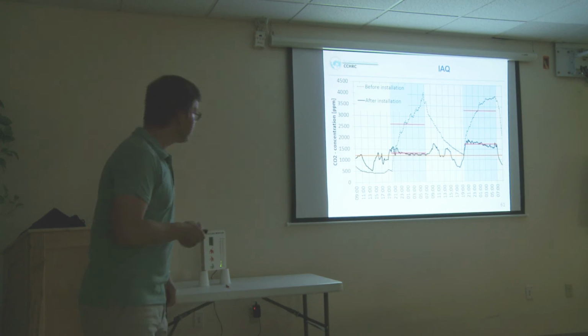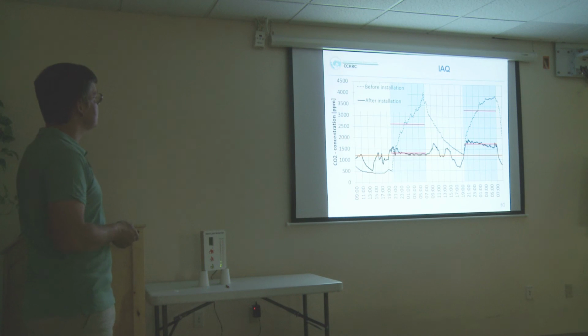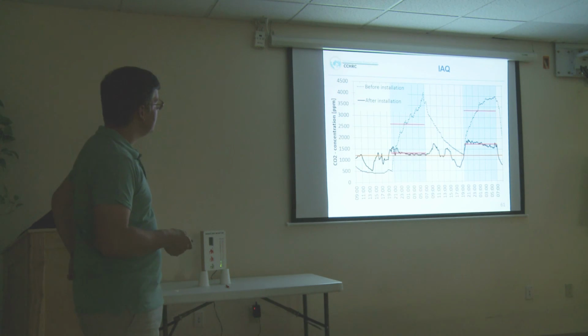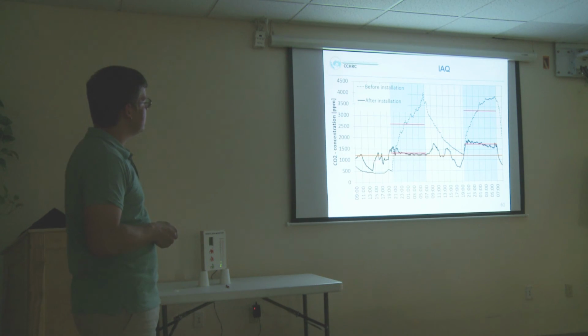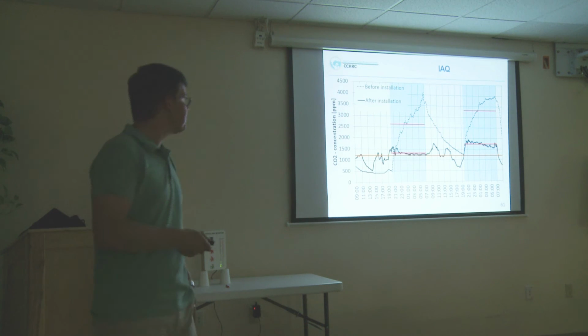So what happened with the indoor environment? We have two nights here as well. This is the chart shown on one of the first slides, and then after we installed the ventilation unit, the nights look like this. We are still a little above 1000 or 1100 ppm, but very close to that, and the second night is also below 2000 at least. You see the ventilation kick in, and now we are at 700 ppm in here.